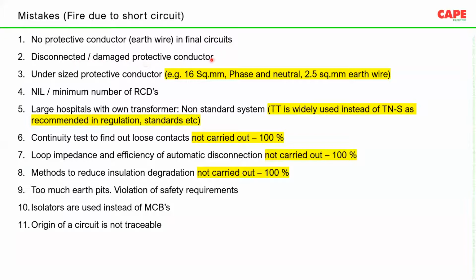And most of the time, the protective conductor is disconnected, undersized protective conductor, no RCDs. Large hospitals with their own transformer go for a non-standard TT system. Continuity tests to find loose contacts are not carried out 100%. Fault loop impedance test is 100% not carried out. Methods to reduce insulation degradation are 100% not available. Too many earth pits. Most of the hospitals, if we walk around, there are hundreds of earth pits installed. This is a violation of safety requirements. Isolators are used instead of MCBs. Origin of circuit is most of the time not traceable.